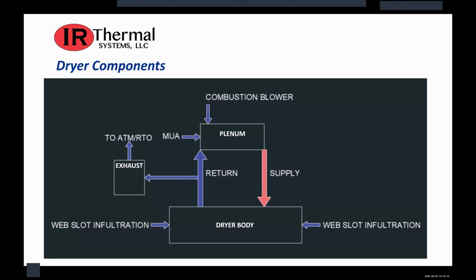So the major components within any drying system are the recirculation air plenum, the dryer body, and the exhaust. Those are absolutely needed. What everybody can typically see, the parts that people kind of overlook, is what each one of those does and where the airflow within them is occurring. So you might have a plenum, where your return air is coming back to and your supply air is coming from, but also typically that's where your makeup air comes into the system. Also, combustion air comes into that system, whereas your return air ductwork is also often used to pull your exhaust air. That exhaust air can also be taken from the dryer body.